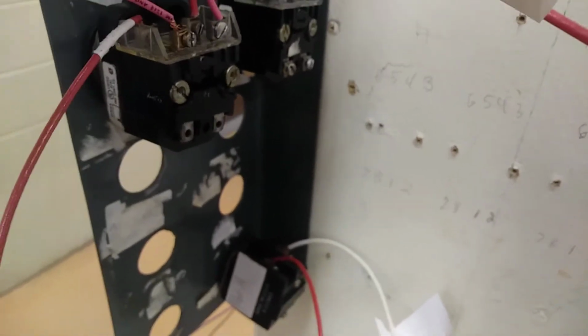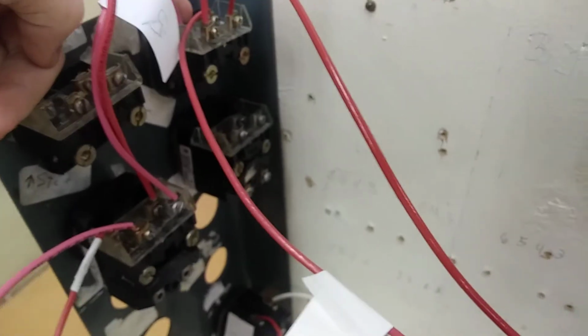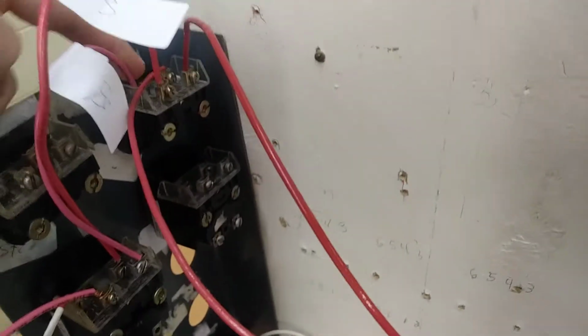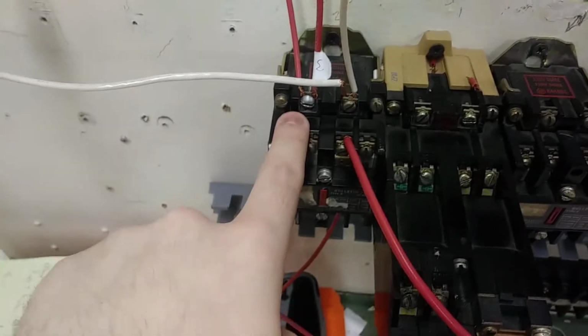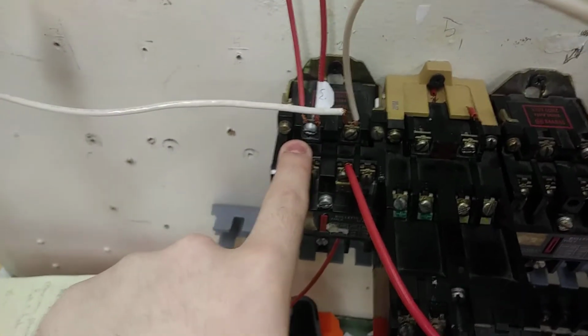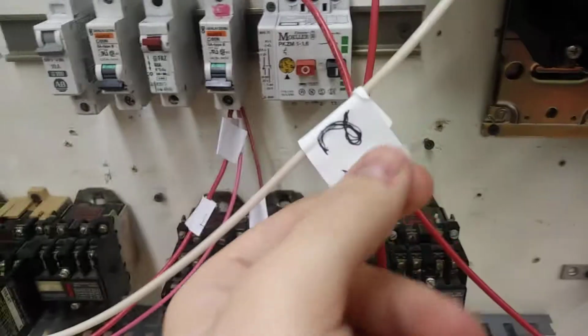Now we're looking at this pink wire going from the normally open over to 5, which is jumping up to our second button, which then jumps over to 6 and is connected to our control relay. Both of these wires are in, and our out is connected to our X2. So now that's the complete circuit for 1 and 2.